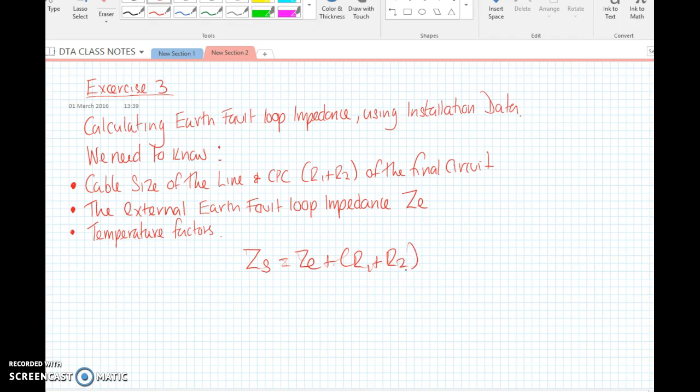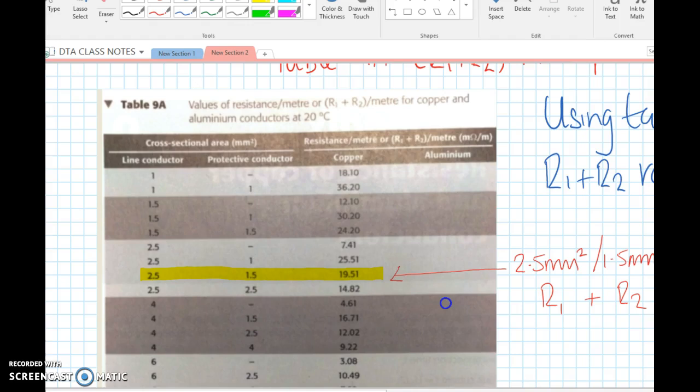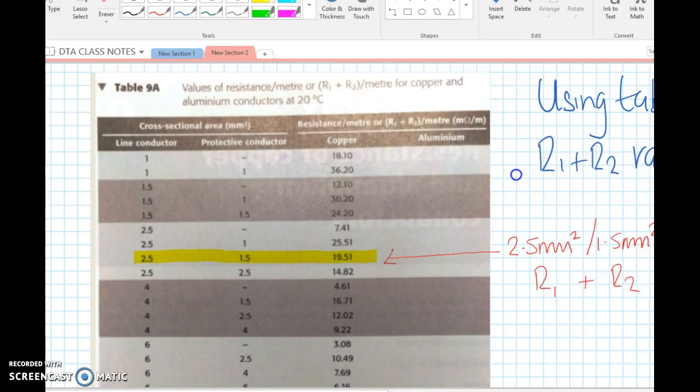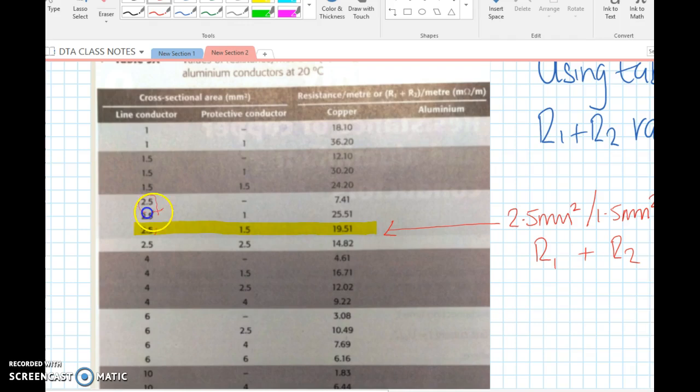Previously when we've looked at earth fault loop impedance, we've written the formula down as ZE plus R1 plus R2. What we're going to do this time is we're going to add a couple of temperature correction factors. This is table 9a, taken from the IET on-site guide.